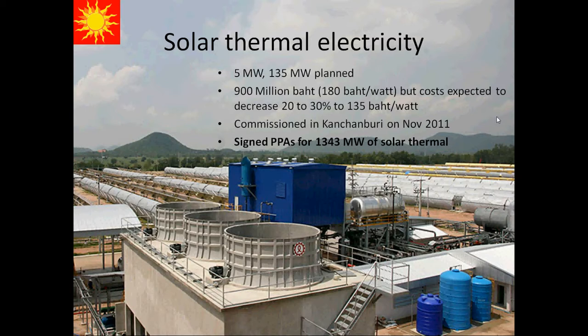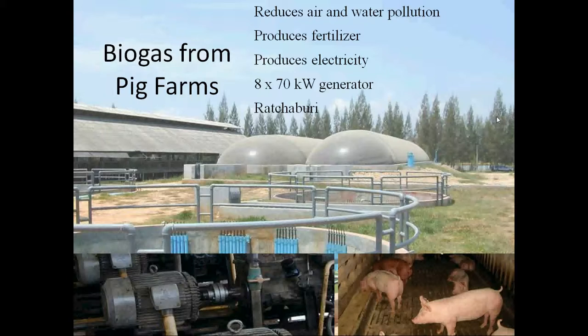Pig farms have been a big one. Prior to the VSPP program, pig farms were a big problem — they smell bad and produce pollution causing problems with local groundwater. These pig farm biomass systems capture the pig waste, make methane with it, and burn the methane in modified diesel generators to produce electricity.